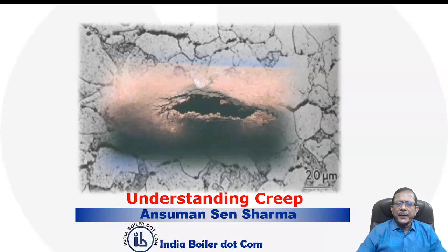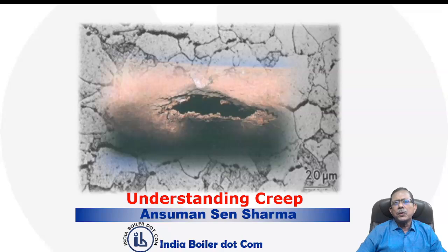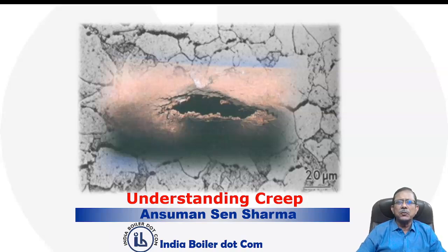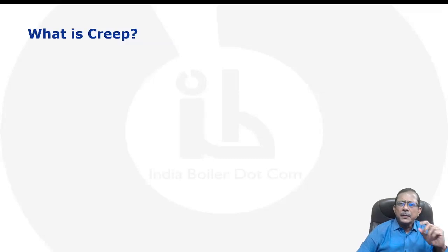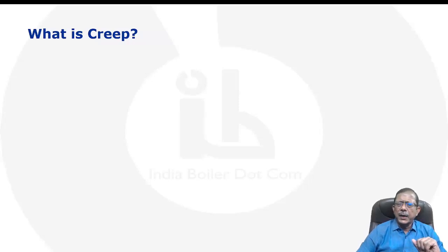After a long time I have come back again with a discussion on tube failure. In this video I am going to discuss about creep. Now creep is something relevant when you are working in a boiler and discussing the degradation of tube health. Many times I get the answer that creep is deformation due to high temperature stress — but that is not exactly true. Temperature plays an important role, but creep is not caused by high temperature; it is affected by high temperature, but not caused by it.